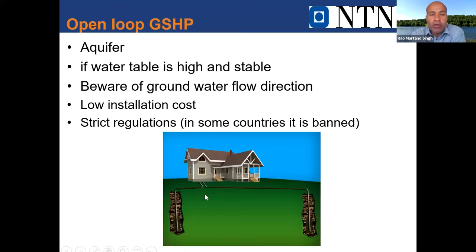Another option is if we have a high water table, then we can use the water directly. You have a pipe, water comes in and water goes out, so you get the energy and then release the water. But this system is very regulated, and it depends on the country, and within countries it depends on the municipal corporations. Some allow this type of system, some do not. In Germany, for example, they are against this system because they worry that when you take the water out, it may become contaminated, and then it's your job to remove those contaminants before putting it back. They're also worried that when water goes in, something may happen and cause pollution, so you cannot put the water back. So some countries don't allow this kind of system, but some do.